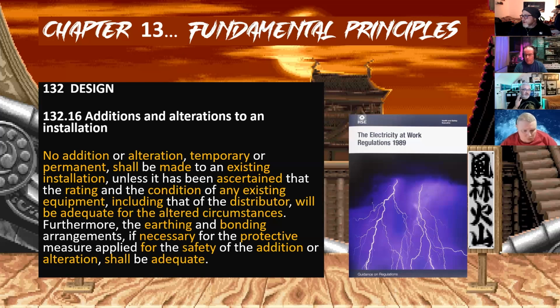When you walk into any domestic installation, go and find the gas, go and find the water, go and check the bonding. When going into commercial activities, go and ascertain the point of intake, the DNO head - is there an earthing conductor present? Is there bonding? If we have records, fine; if not, we should be going out and verifying it in some form and including all that in your pricing. Why? Because of 132.16 - you need to ensure the protective measures are there, and that what you do doesn't make it any worse.